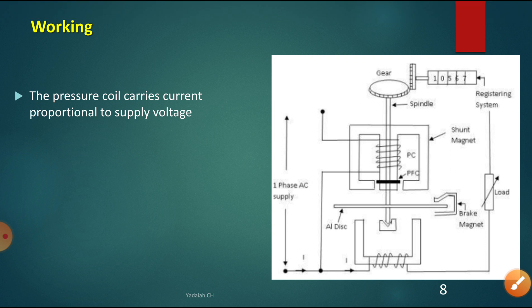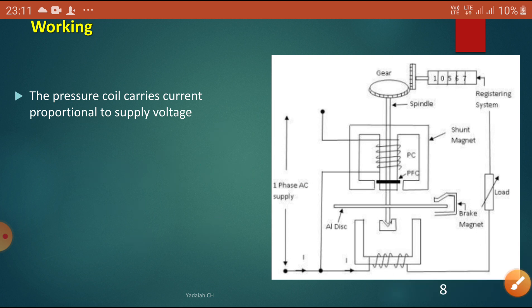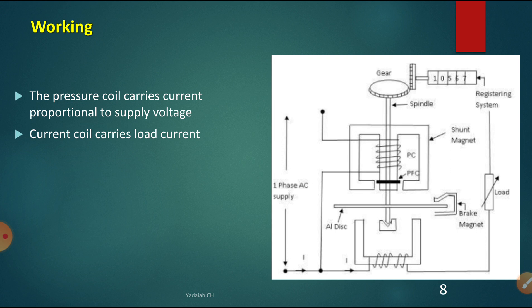The pressure coil carries the current proportional to the supply voltage. The single-phase supply is 230 volts plus or minus 10 percent. If the voltage is more, more flux is produced; if voltage is less, less flux is produced — it is dependent on the supply voltage. Next, the current coil carries the load current.